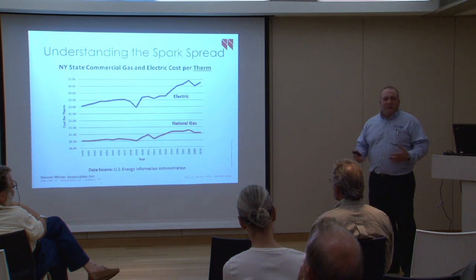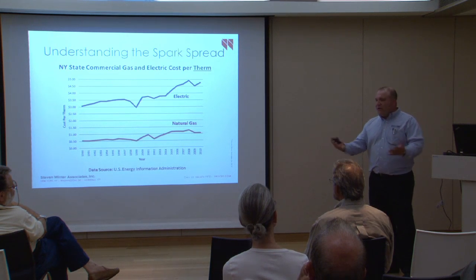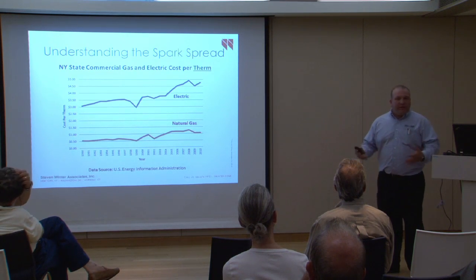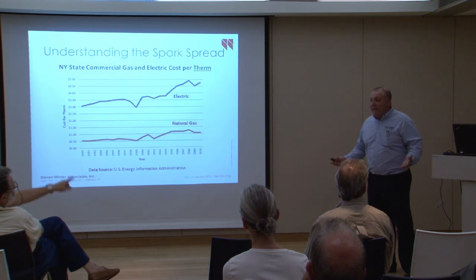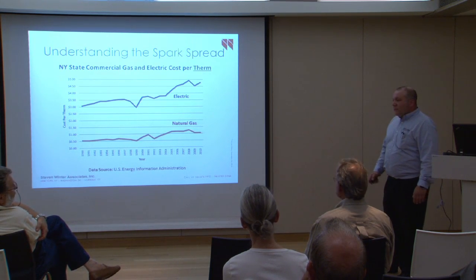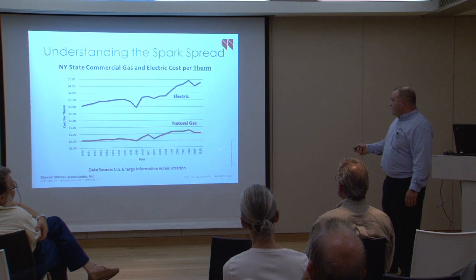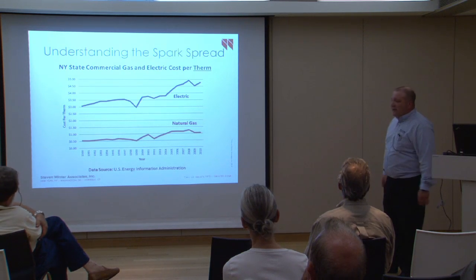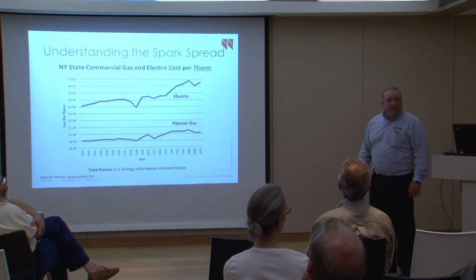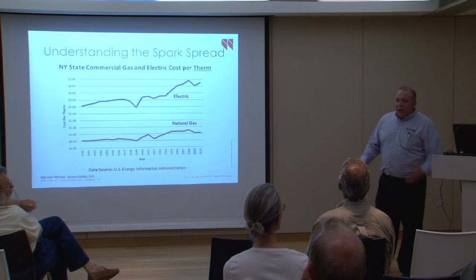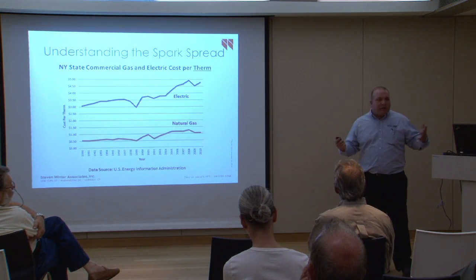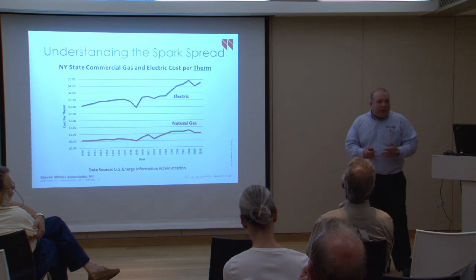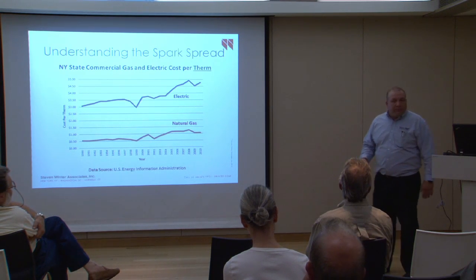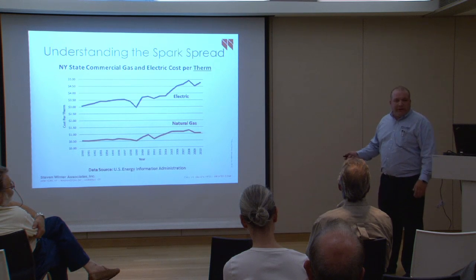All these systems require a pretty fast payback. As with other energy efficiency upgrades, there needs to be a good payback for it to happen. Natural gas cost is going down now, so if you extended this graph out to 2015 you'd see a downward trend, meaning an even bigger spread today than in 2000. We aim for paybacks under 5 years for a conventional cogeneration project—4 years is a nice target, sometimes 3. NYSERDA funding does a lot to help that.